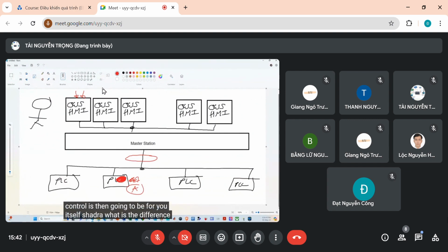Shadrach asks, what is the difference between DCS and SCADA? DCS is all on one geographical site. SCADA takes us a bit away from the site - we have information that needs to be sent across an unprotected, potentially unsafe, potentially slow network. SCADA is essentially the same as DCS, but DCS is on one site while SCADA is going to be over a wide area. Those are the differences we can encounter.